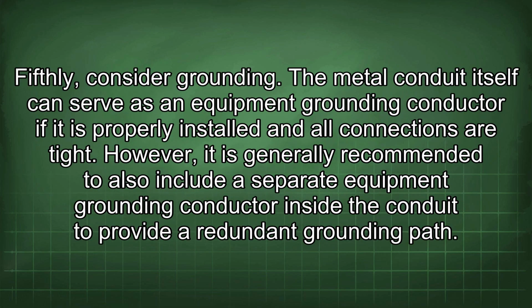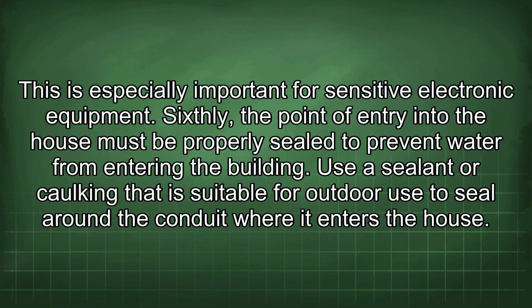Fifthly, consider grounding. The metal conduit itself can serve as an equipment grounding conductor if it is properly installed and all connections are tight. However, it is generally recommended to also include a separate equipment grounding conductor inside the conduit to provide a redundant grounding path. This is especially important for sensitive electronic equipment.